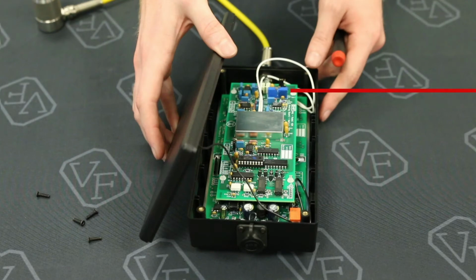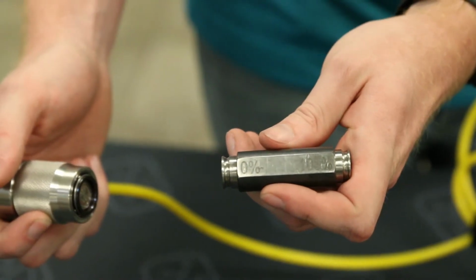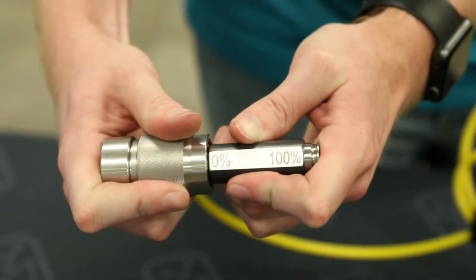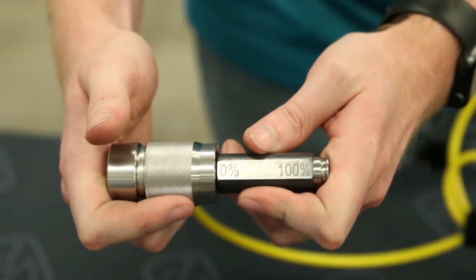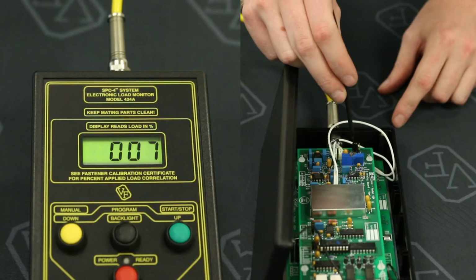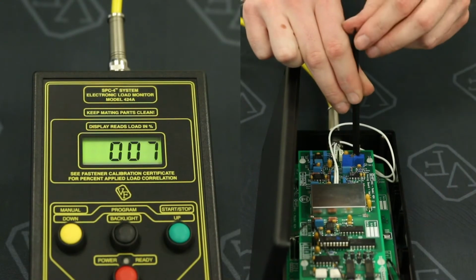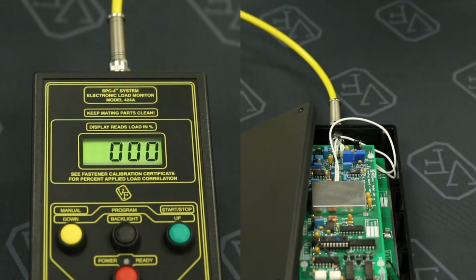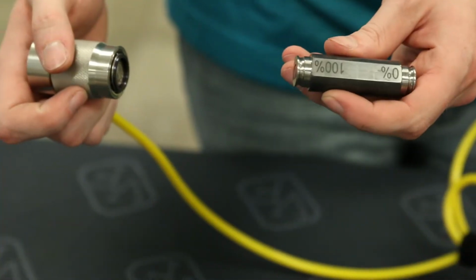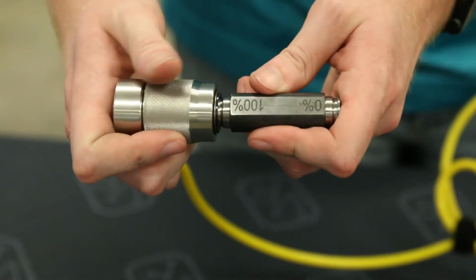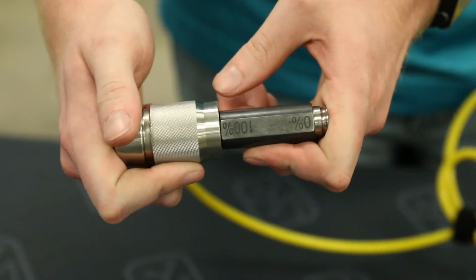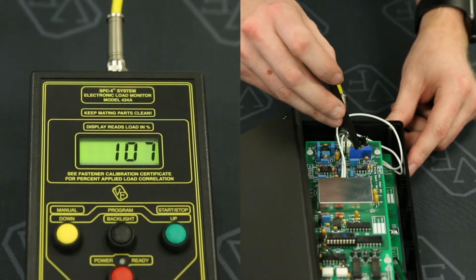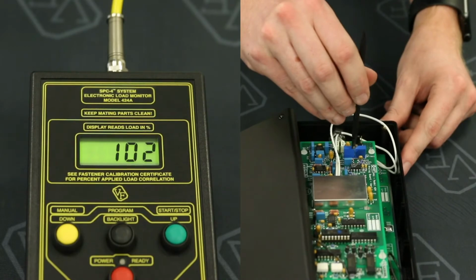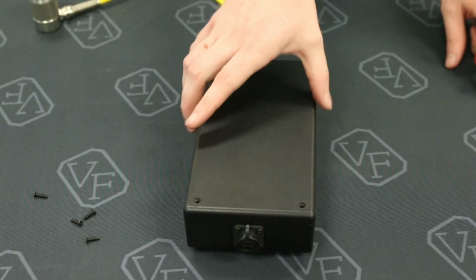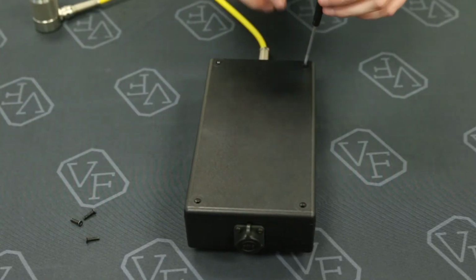With the 424A unit on, attach the 0% end of the calibration gauge to the 424A probe. Adjust the offset potentiometer as necessary until the 424A LCD reads 0%. Remove the calibration gauge and then attach the 100% end of the gauge to the 424A probe. Adjust the gain potentiometer so that the display shows 100%. Perform a calibration check to confirm proper calibration has been achieved and reattach the rear of the 424A enclosure.